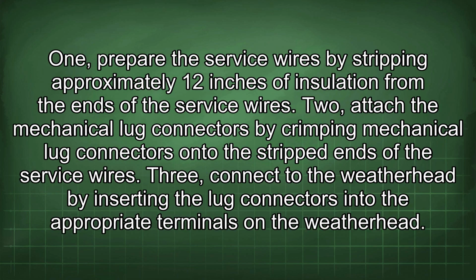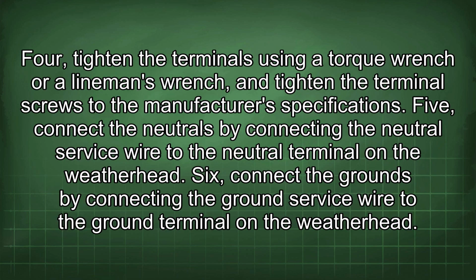1. Prepare the service wires by stripping approximately 12 inches of insulation from the ends of the service wires. 2. Attach the mechanical lug connectors by crimping mechanical lug connectors onto the stripped ends of the service wires. 3. Connect to the Weatherhead by inserting the lug connectors into the appropriate terminals on the Weatherhead. 4.